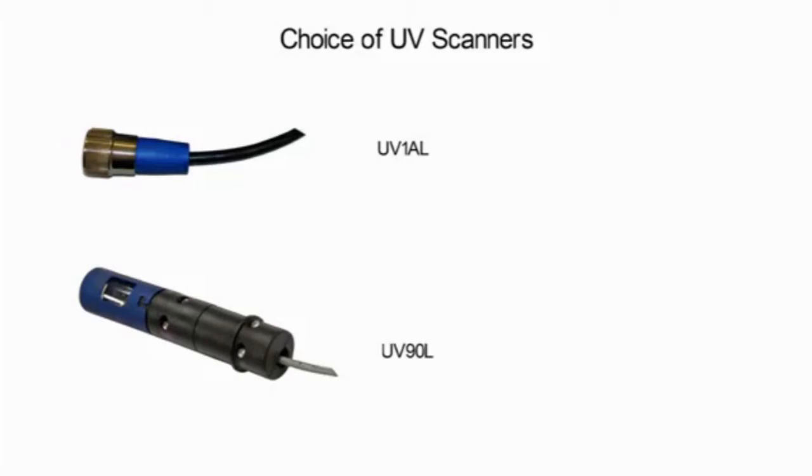The UV-90L provides a field wireable terminal block. The UV-1AL and UV-90L ultraviolet flame scanners are non-self-checking and should be applied only to burners that cycle a minimum of once per 24 hours.